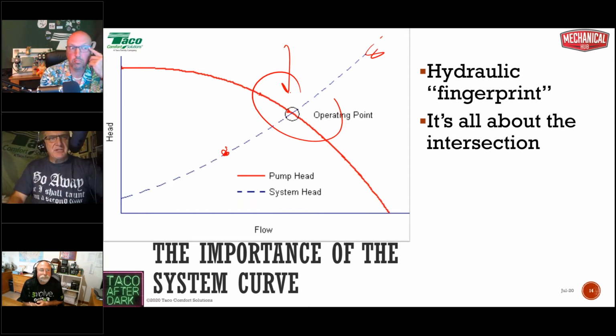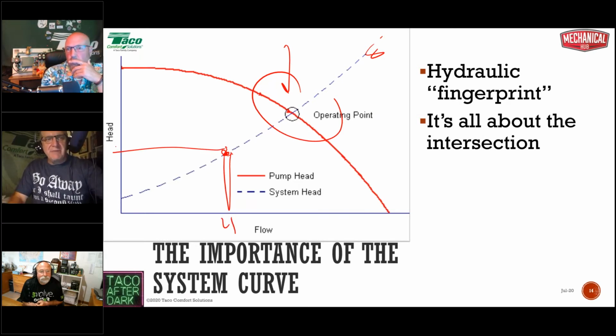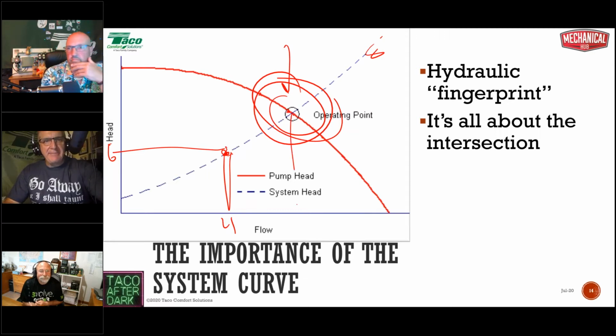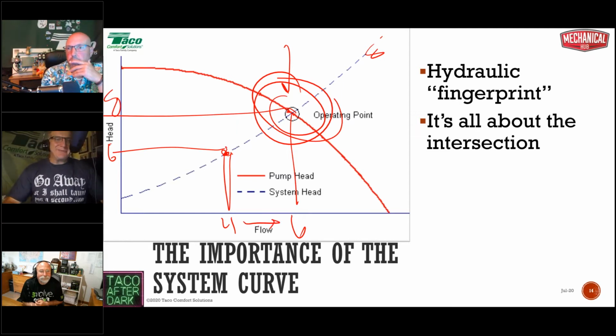Happens all the time. So we can go through an awful lot of business to find 4 gallons a minute at 6 feet of head. And the minute we slap a circulator on there, it ain't never working at 4 at 6 unless we're really lucky. It's going to work right here where the system curve intersects the pump curve every single time. And if that happens to be 6 gallons a minute at, let's say, 8 feet of head, well, 4 to 6 gallons a minute, that's only 2 gallons a minute. No, man, that's 50% more flow than we need under design conditions.